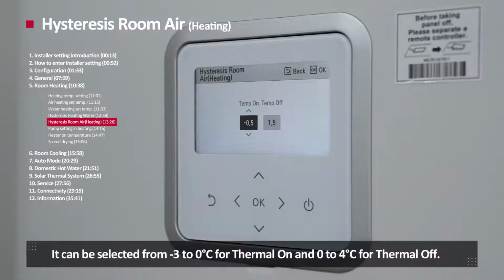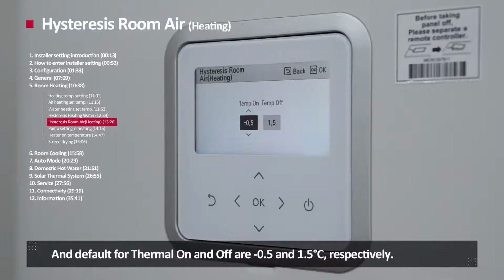It can be set from -3 to 0 degrees Celsius for Thermal On, and 0 to 4 degrees Celsius for Thermal Off. And default for Thermal On and off are -0.5 and 1.5 degrees Celsius respectively.